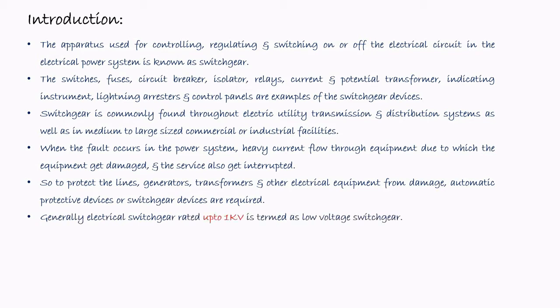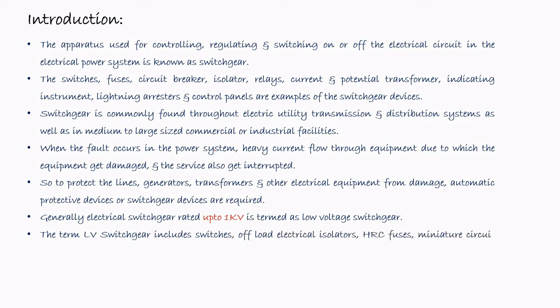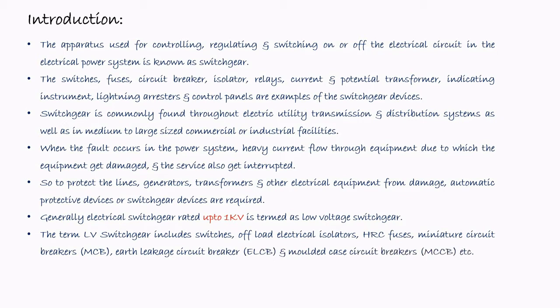Generally, the electrical switchgear rated up to 1 kilovolt is termed low voltage switchgear. And the term low voltage switchgear includes the switches, off-load electrical isolator, HRC fuses, miniature circuit breakers, earth leakage circuit breakers, molded case circuit breakers, etc. So, the earth leakage circuit breaker or ELCB.